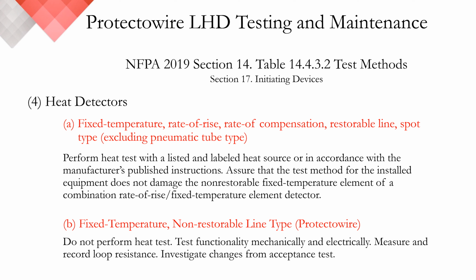Testing of linear heat detection is established through NFPA 72, Section 14, under test methods for initiating devices, more specifically, heat detectors. Under Table 14.4.3.2, NFPA identifies heat detectors in two classes. The first being a fixed temperature restorable or spot type heat detector, and the second being a fixed temperature non-restorable or line type heat detector.